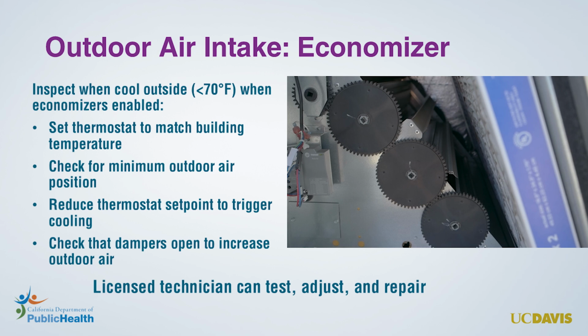As we learned in an earlier module, this is an actuated damper assembly that can increase outdoor air for cooling the building when conditions permit. Most of the time, the dampers are stable at the minimum outdoor air position. When the thermostat calls for cooling and the temperature outside is below a set point, the damper should open up to 100% outdoor air. You'll want to inspect your economizer assemblies and make sure the system is working.